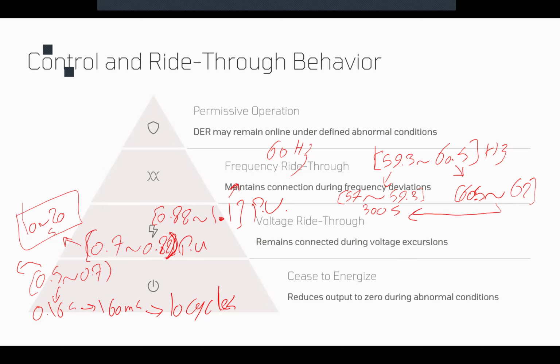Now, another aspect of the ride-through is the cease to energize. Let's say we go beyond those intervals for ride-through, for both frequency and voltage ride-through. Now what happens? It's not that they instantly could trip. There is another requirement, which we call cease to energize. Let's first define the difference between cease to energize and trip. When we talk about the cease to energize, it means to stop injection of the current, but we are electrically still connected to the grid. When we talk about the trip, trip means fully physically disconnected from the grid. In cease, we are connected to the grid, we just don't inject current. In trip, we are disconnected from the grid.